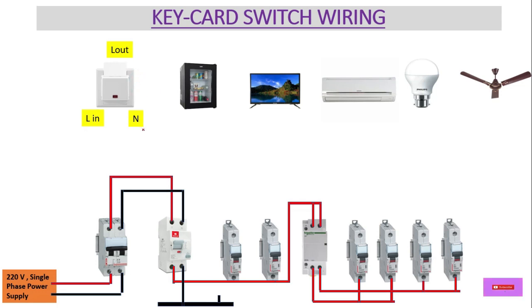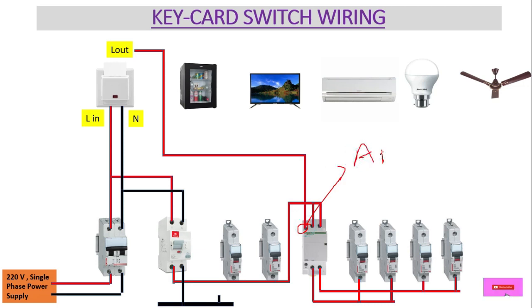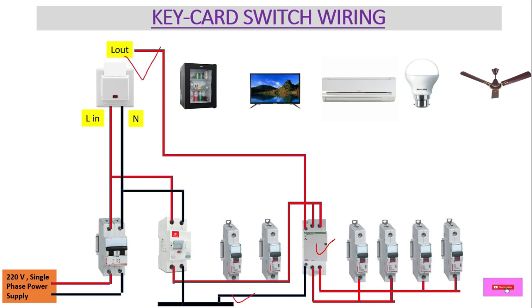Now let's come to the key card switch wiring, which is the main focus. For L-IN, we connect the phase wire to the input terminal of the key card switch, then neutral to N. From L-OUT — sometimes labeled 'Load' — it connects to the A1 coil supply terminal of the contactor. At A2, neutral is provided from the neutral busbar. In this way, the contactor coil gets its power supply controlled through the key card switch.